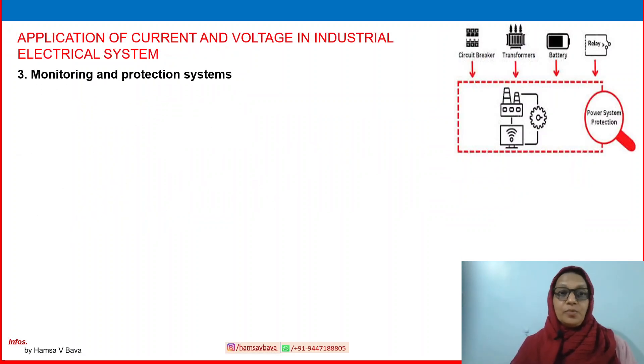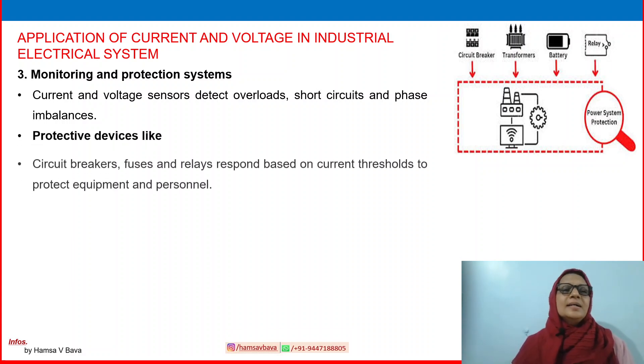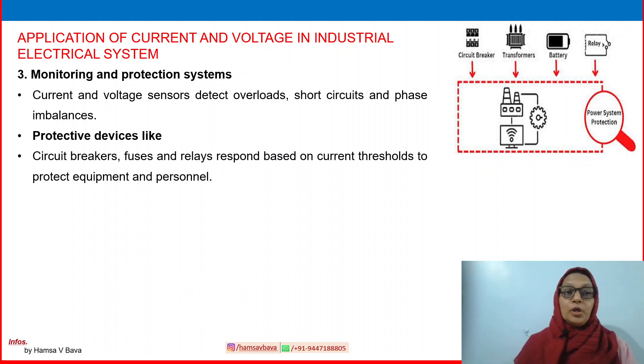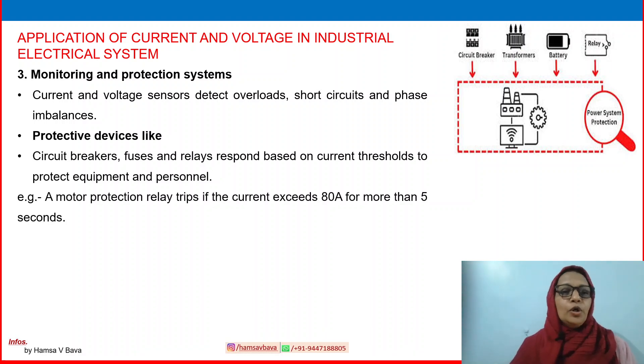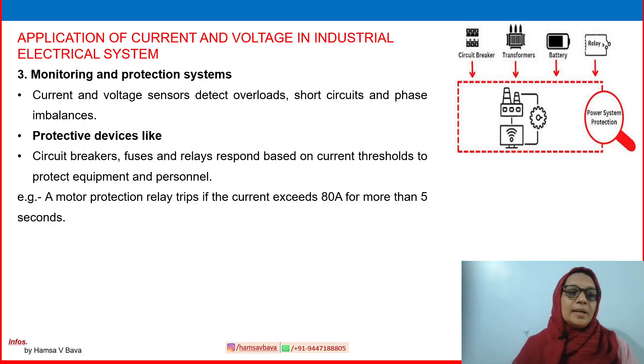Monitoring and protection systems are very crucial. Current and voltage sensors detect overloads, short circuits, and phase imbalances. Protective devices like circuit breakers, fuses, and relays respond based on current thresholds to protect equipment and personnel. For example, a motor protection relay trips if the current exceeds 80 amperes for more than 5 seconds during operation — that is how the protection relay protects the circuit as well as personnel.